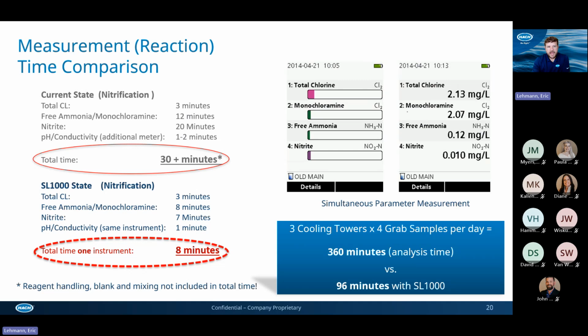So let's think about the reaction time and time comparison. We'll call this the current state, and just for example, we're looking at nitrification parameters: total chlorine, monochloramine, free ammonia, nitrite. For each of these parameters, I need to pull a sample and wait 3 minutes for total chlorine. For free ammonia and monochloramine, that's a 12-minute reaction time. For the nitrite, that's a 20-minute reaction time. And then pH and conductivity, once calibrated, don't take very long, maybe 1 to 2 minutes. But if I'm running all 4 of these parameters, just the reaction time is going to take about 30 minutes.